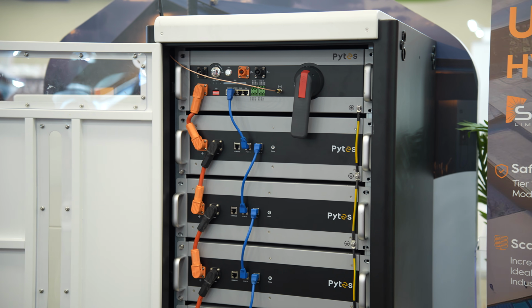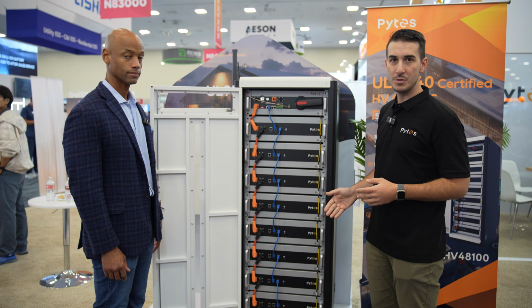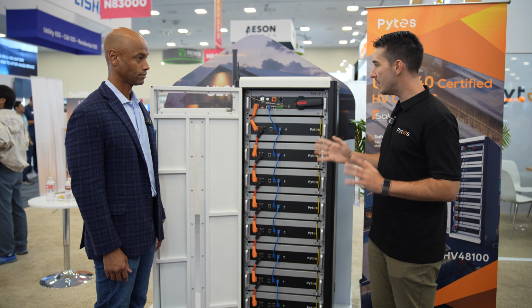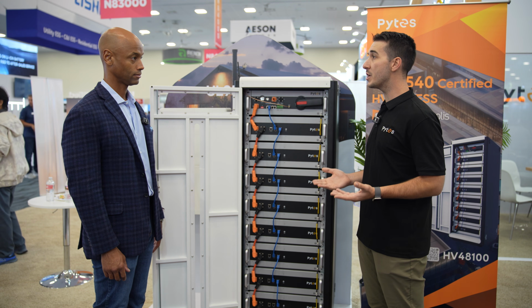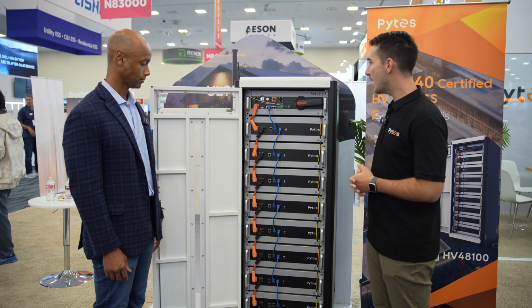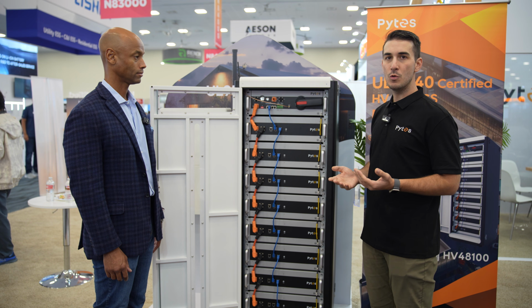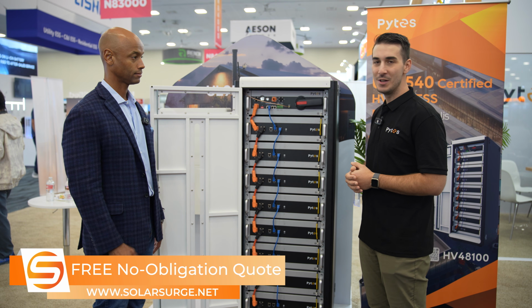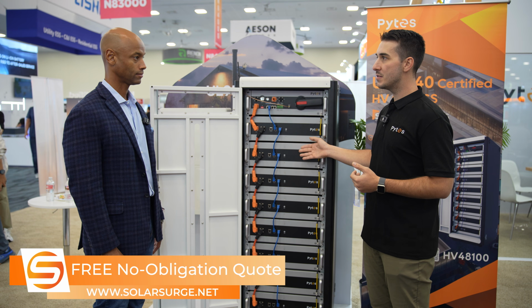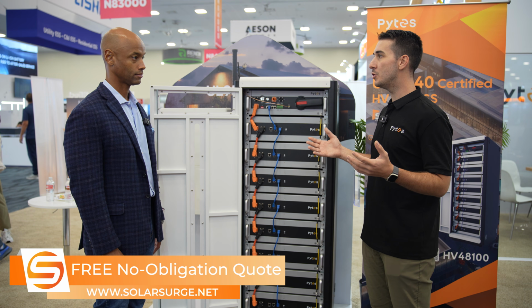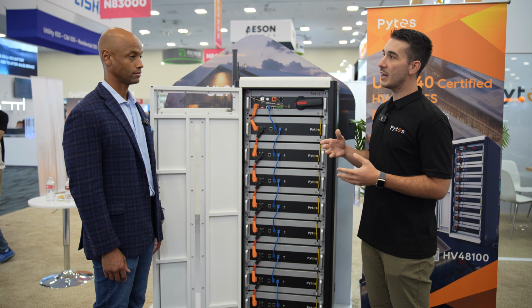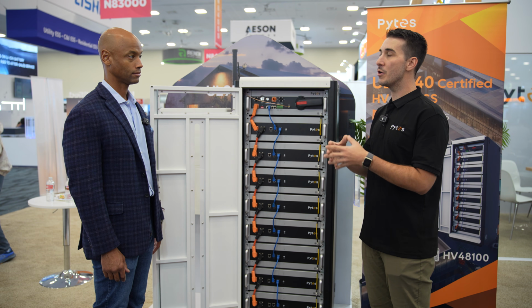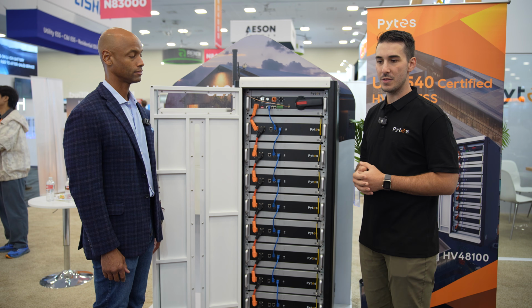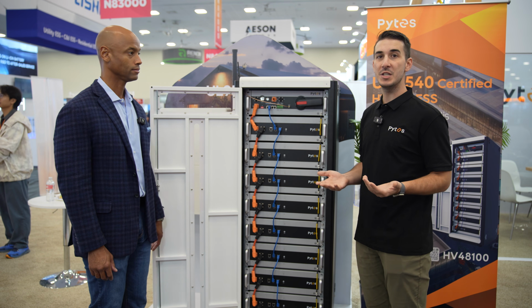This here we see is a fully populated cabinet with 8 modules. That would be right in the neighborhood of about 40 kilowatt hours of storage in this cabinet. What we can do, for example, with an inverter such as a Sol-Ark 30K, I'll just use that example, you can have up to 6 cabinets of 8 modules connected to a single inverter, and then you can have that many batteries per each inverter in the system. I think for scalability with the Sol-Ark 30K, you can do up to 10 inverters in a system.